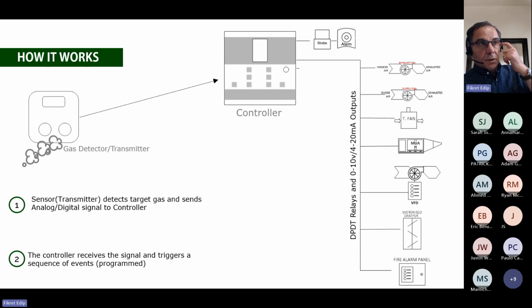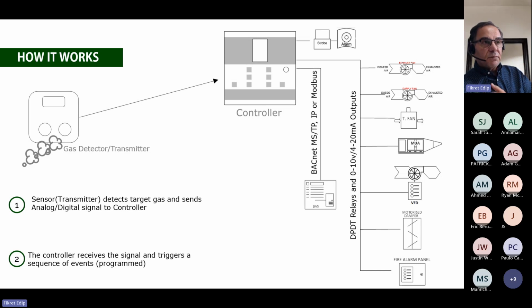And furthermore, I can turn on a strobe and horn to send an alarm to the supervisory office. One step further, I can send out a signal to the outside world, to the building management system, over BACnet or Modbus or any other type of protocol that is being used. So in a nutshell, the sensor transmitter detects gas, translates that into a signal, analog or digital, and goes to the controller. The controller takes that command and activates the sequence of operation that has been programmed in it by the poor programmer. Then it does one of those. If there's a VFD, it starts the VFD. If there's a makeup unit, it's going to start the makeup unit, etc.